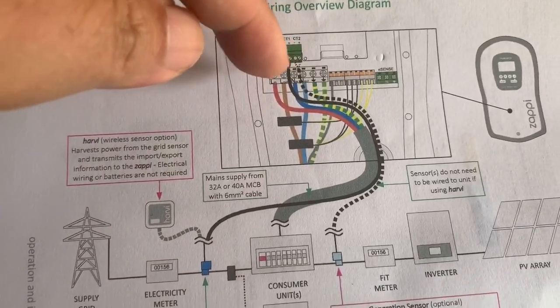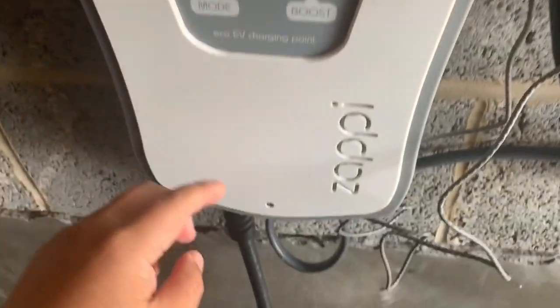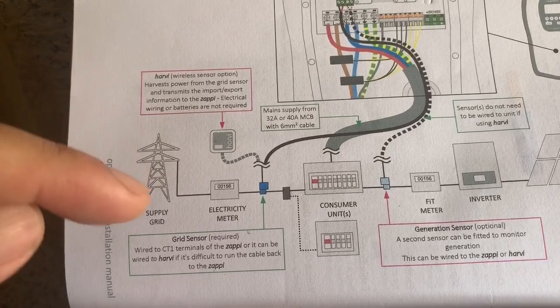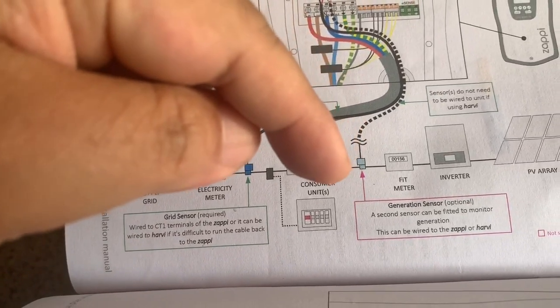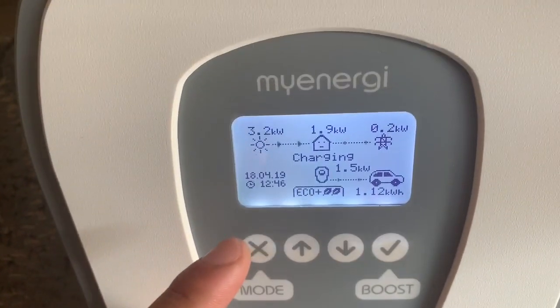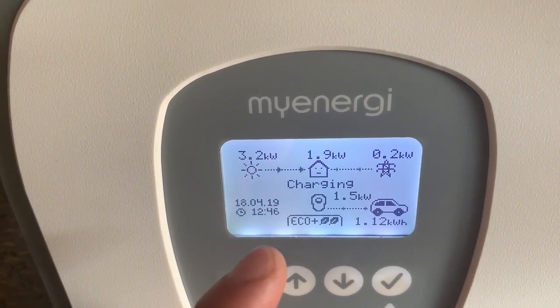Here we have the circuit diagram — live, neutral, and earth are all wired into this unit. The more important thing here is the CT clamps. You've got one for the supply grid going through the electric meter and then to the consumer unit, and a second one which I recommend because this will give you a better, more accurate readout of your solar generation and makes it easier for the Zappi charger to see what's being generated and give you the best total charge from that generation.